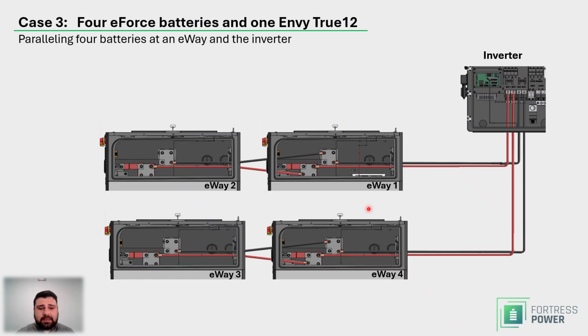The only thing that I would like to add here is a note about communication. Previously it was 3, 2, 1. Here it's going to be 4. eWay 4 will communicate with eWay 3. eWay 3 will communicate with eWay 2, and eWay 2 communicates with eWay 1, which in its turn communicates to the inverter.